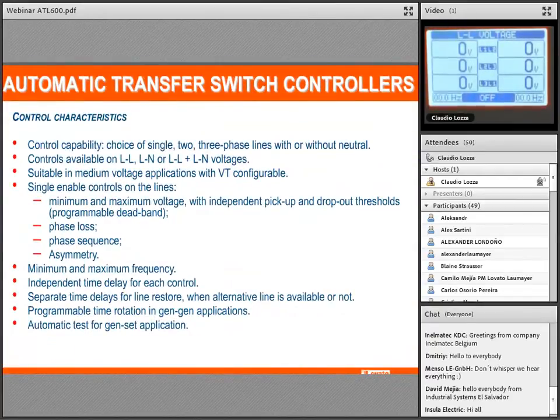So this is the measurement the controller performs. I can manage single line, 2 or 3 phase systems with or without the neutral. I can select on which configuration to do the control, for example, the voltage line to line or the voltage line to neutral, all together. The controller can be used in a medium voltage application using the VT. I can configure the VT, and the visualization is with the real value on the primary of the VT.